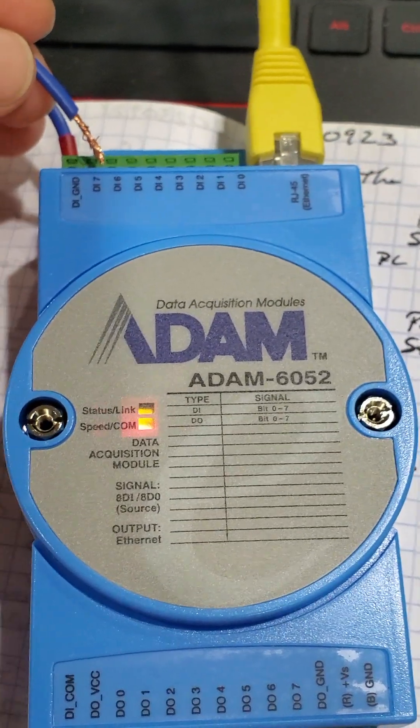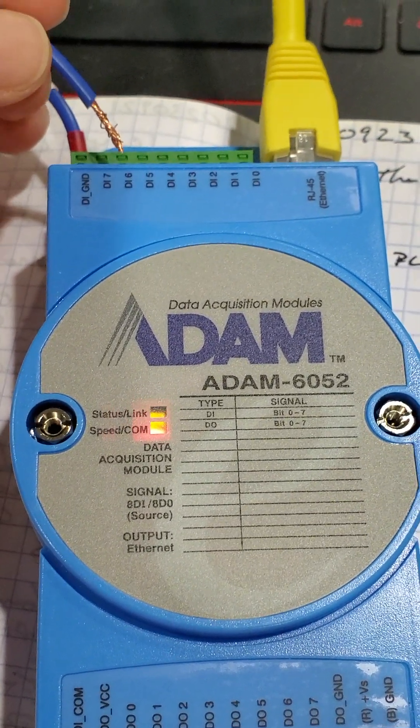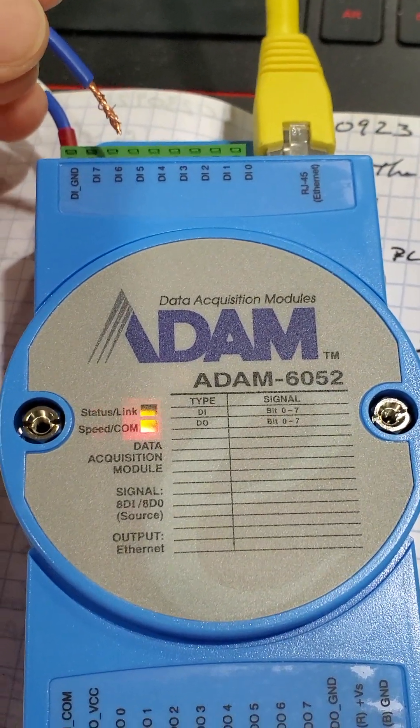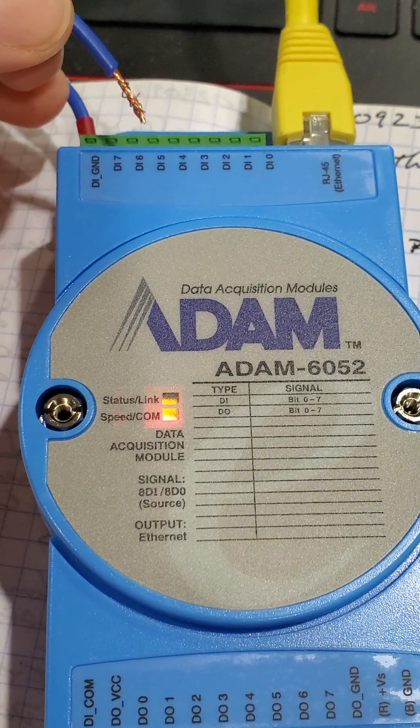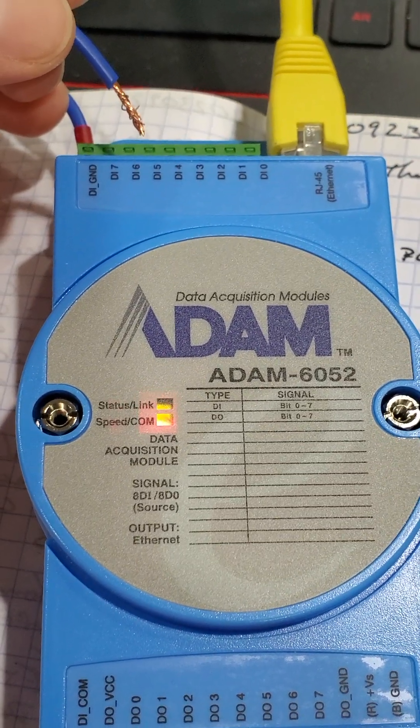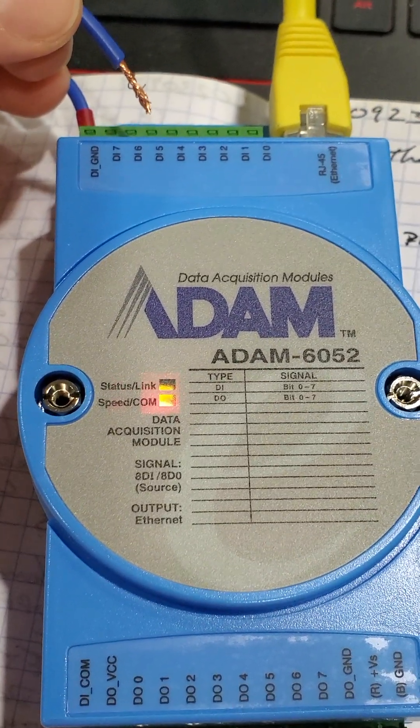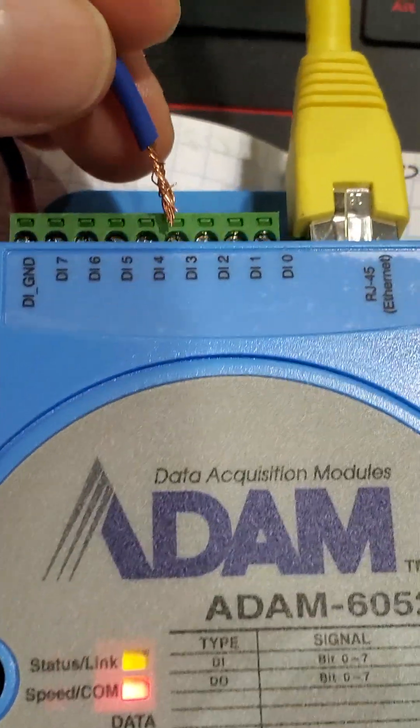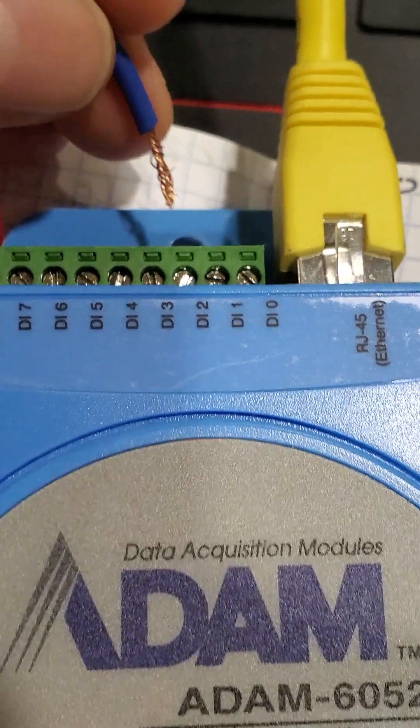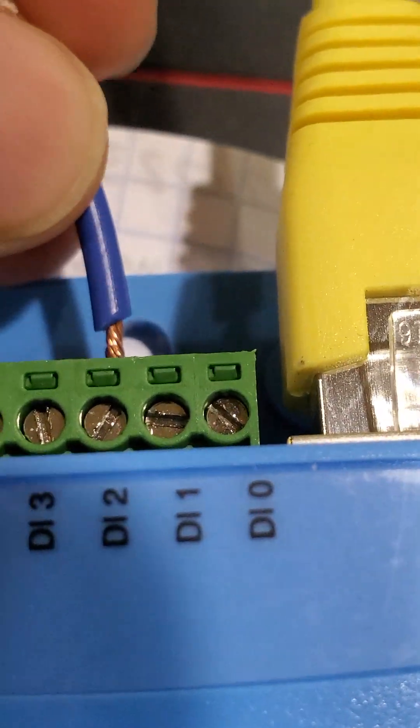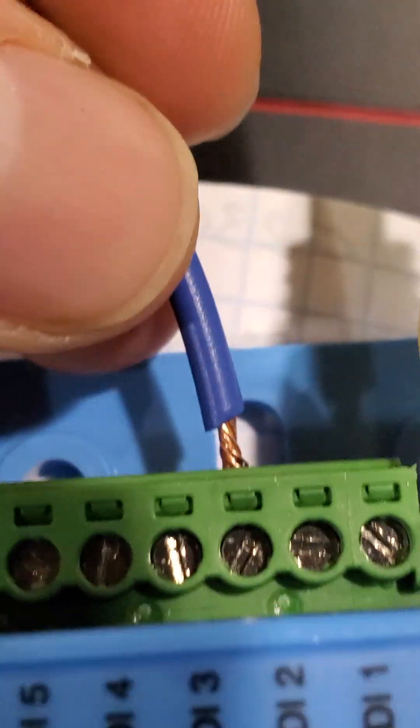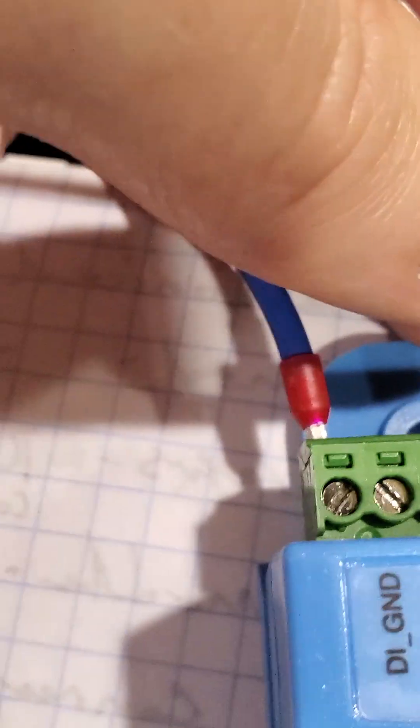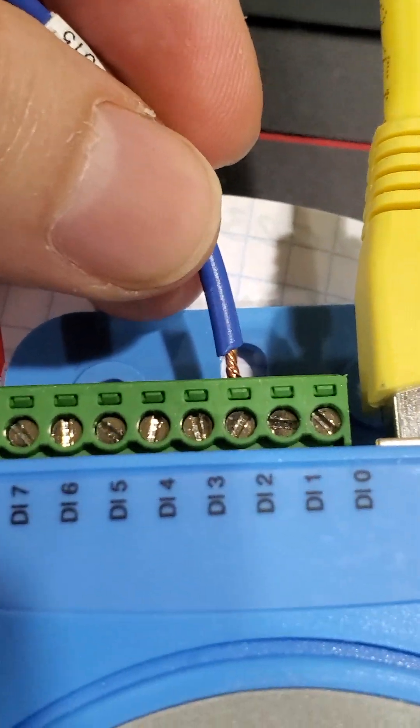Now inside of this module there's a jumper, and you'd have to switch that jumper to the wet contact position, but by default it's set to the dry contact position. And so any of these that I contact that I actually touch, they're now shorted to ground for instance.